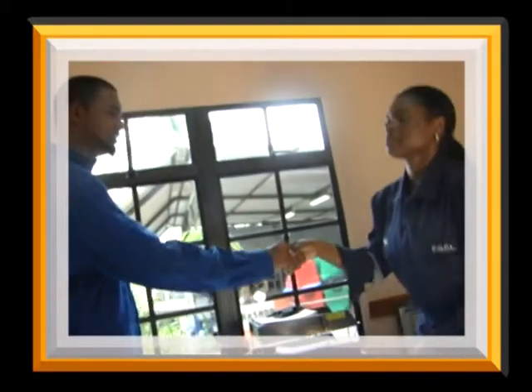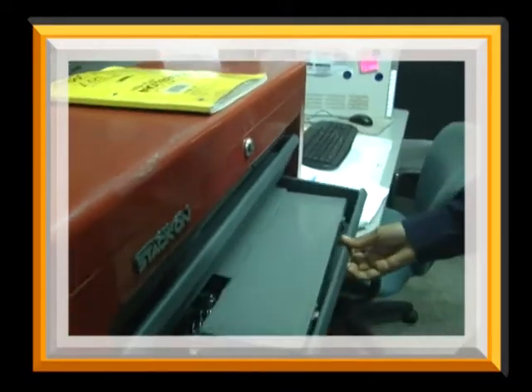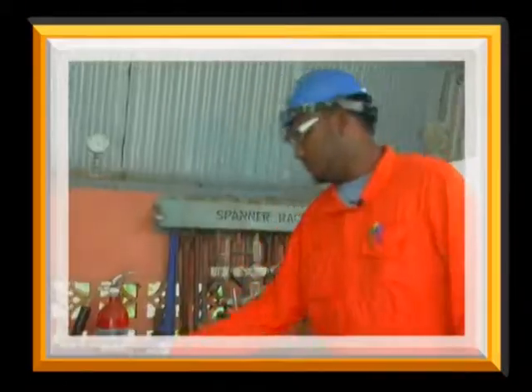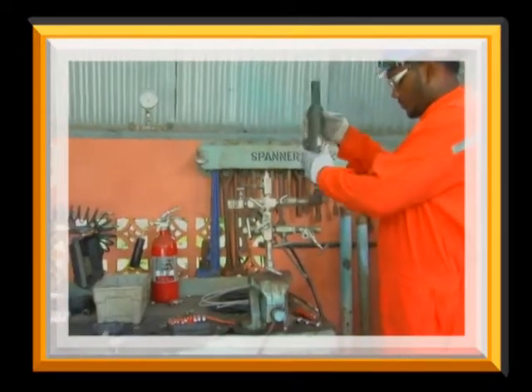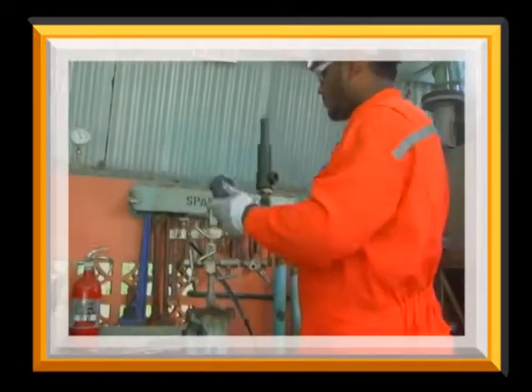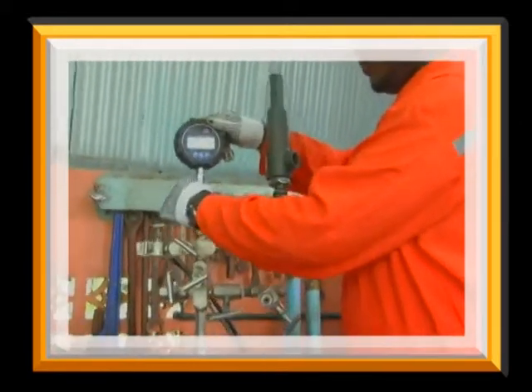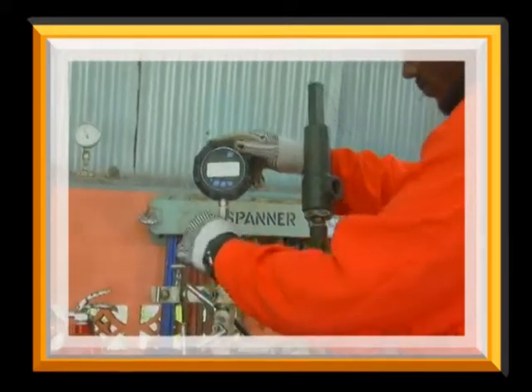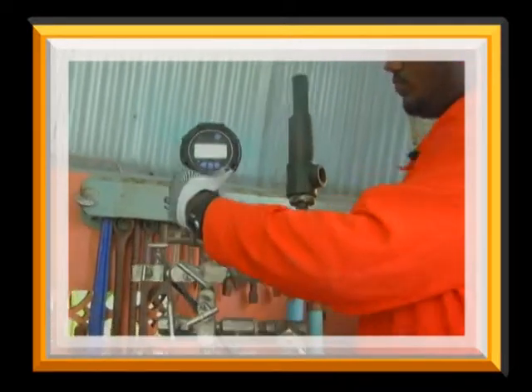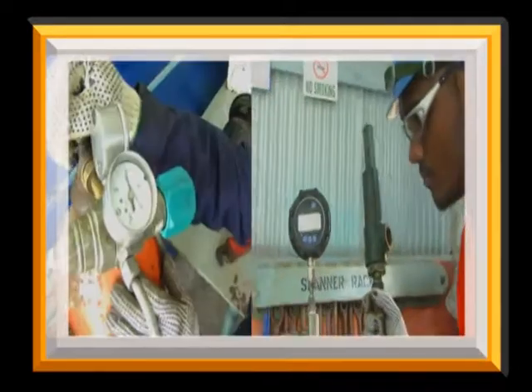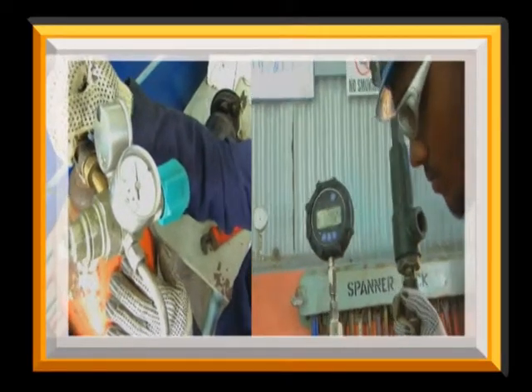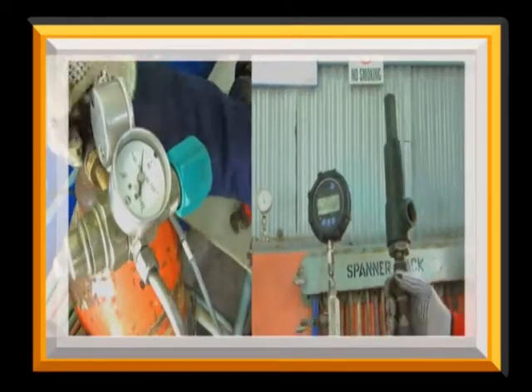The customer is then given a copy of the work request form, and the duplicate is left for documenting purposes at PGCL. Tools for the job are checked in and signed off using our tool log process. The pressure safety valve is installed onto the manifold. The pressure indicator, digital gauge, is then installed onto the manifold. An as-found check is then carried out on all items to be calibrated before proceeding.